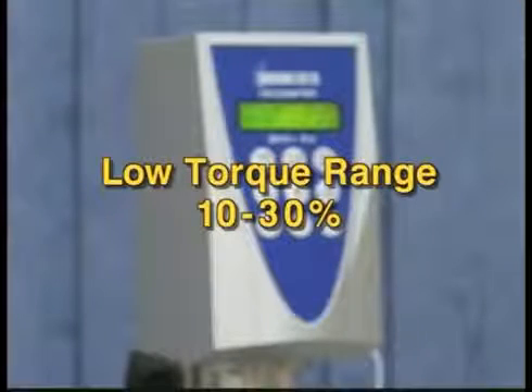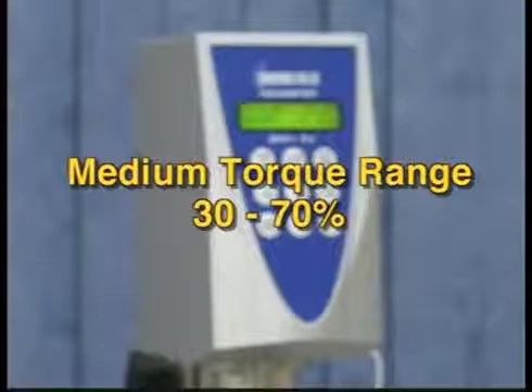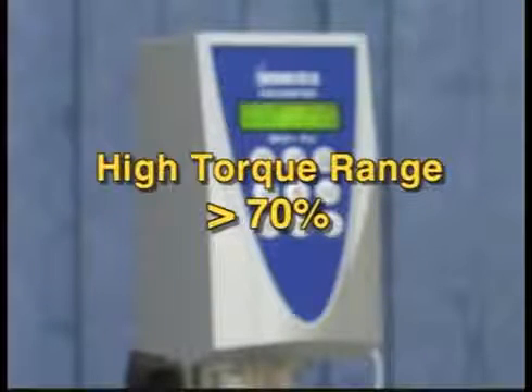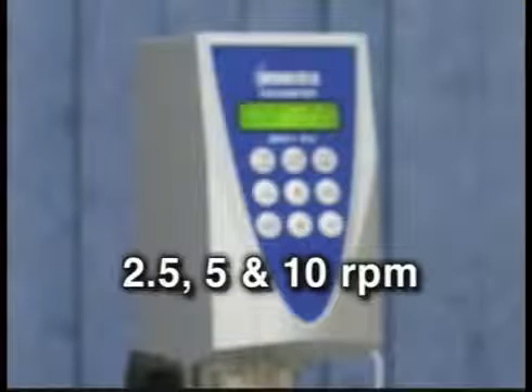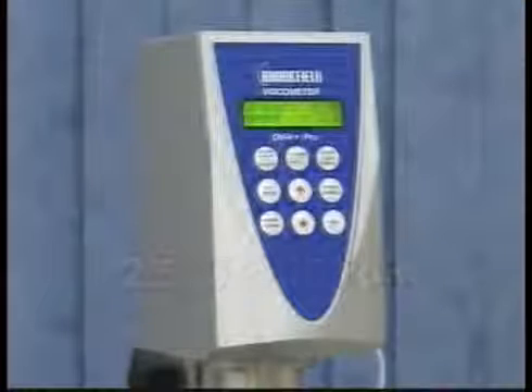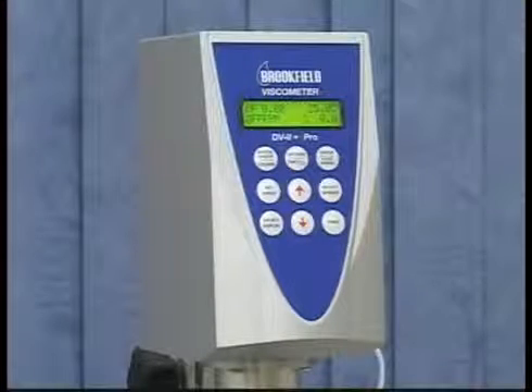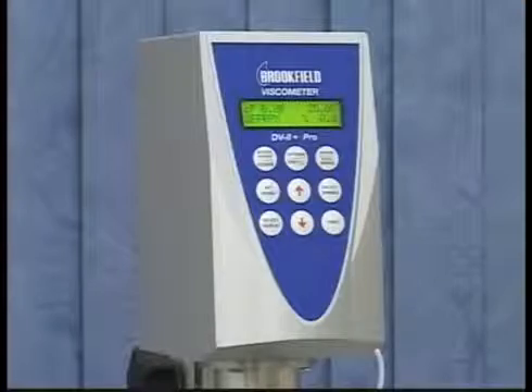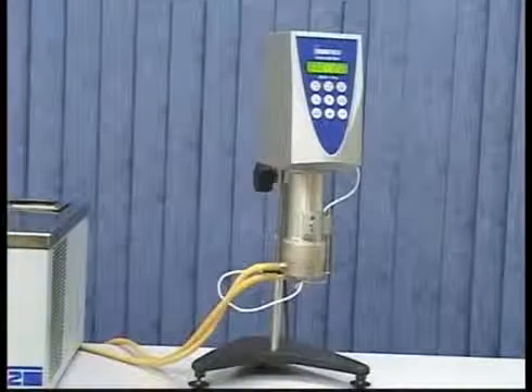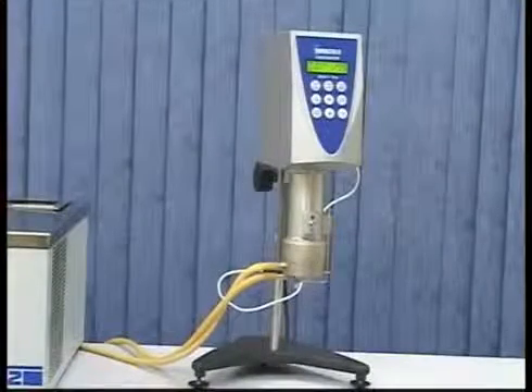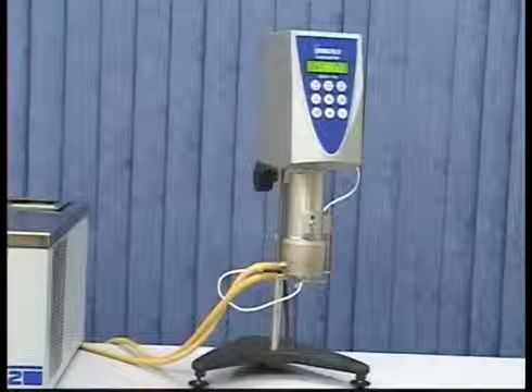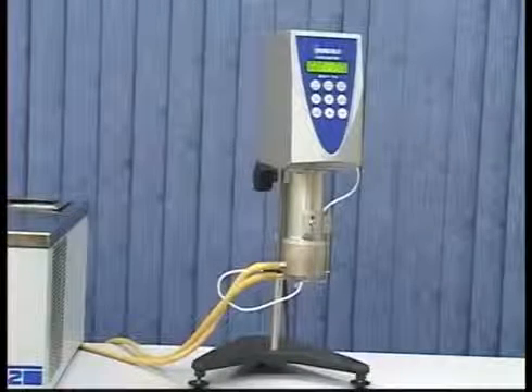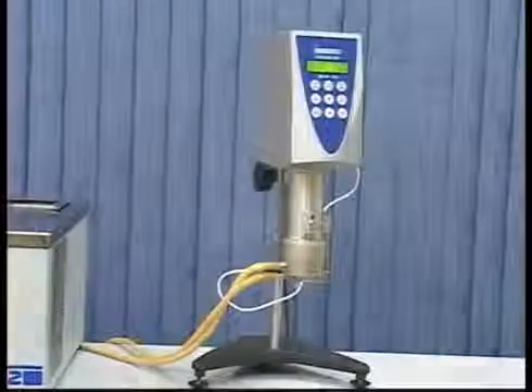A low torque range would be 10 to 30%, a medium range 30 to 70%, and a high torque range above 70%. For this example, we will choose speeds of 2.5, 5, and 10 RPM. This will check the linearity of the spring on this instrument through its full range. Although the equivalent torque ranges will not get us up to 80 to 90%, this is still a valid test which uses the speeds that are available in the instrument.